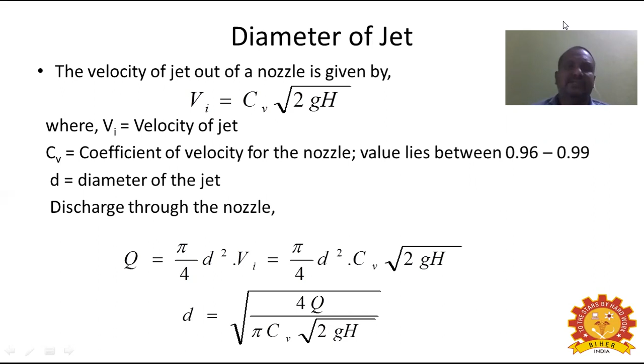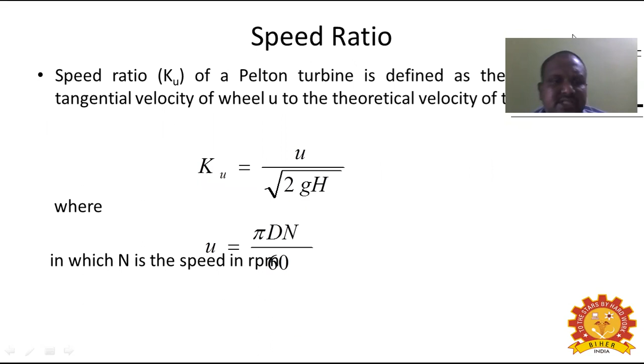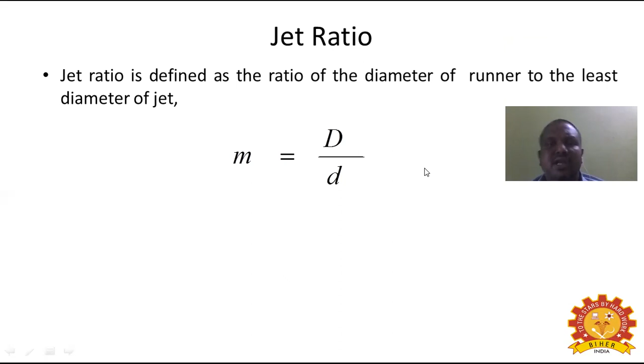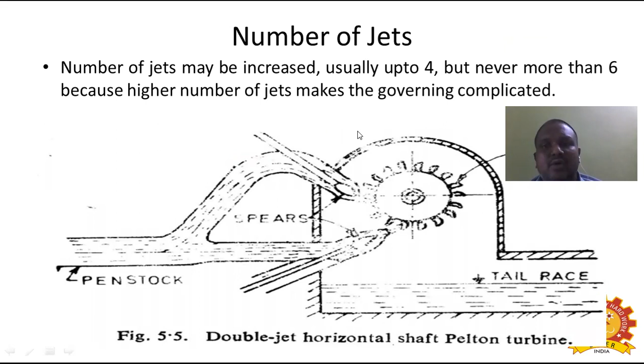Speed ratio. The speed ratio Ku of a Pelton turbine is defined as the ratio of the tangential velocity to the theoretical velocity of the jet. Ku is equal to U divided by root of 2gh, where U is pi D N by 60, and N is the speed in RPM. Jet ratio is defined as the ratio of the runner diameter to the least diameter of the jet, m is equal to capital D by small d. The number of jets is increased, usually 4, but never more than 6, because a higher number of jets makes governing complicated. Double jet is shown in the diagram.